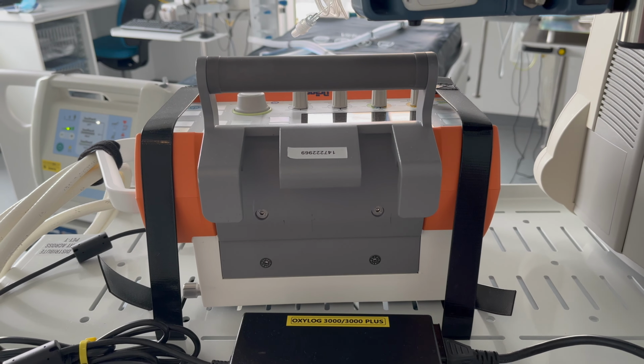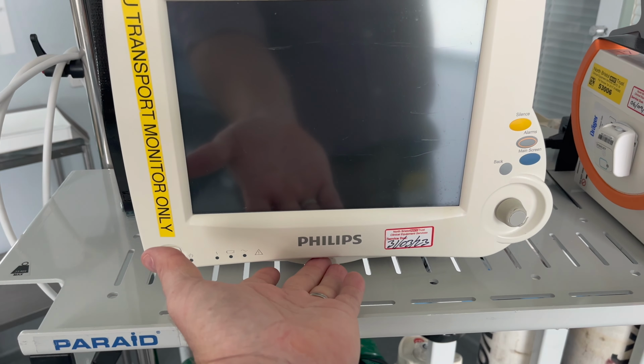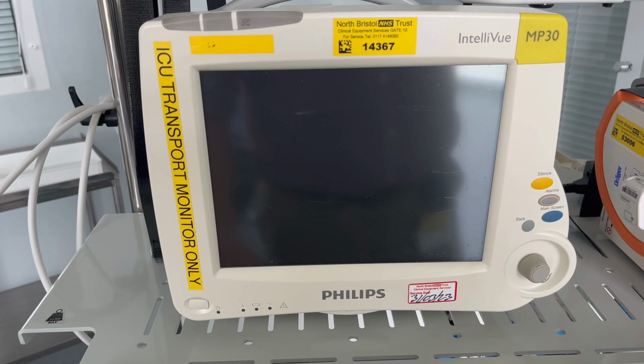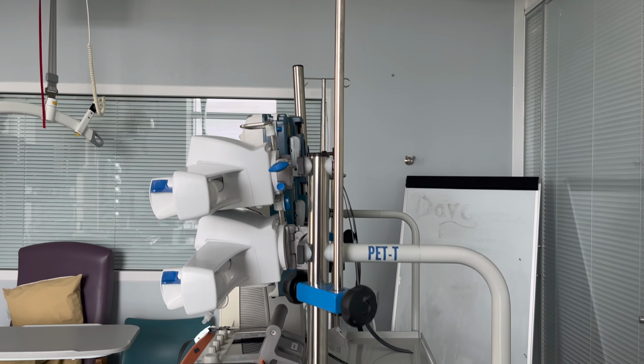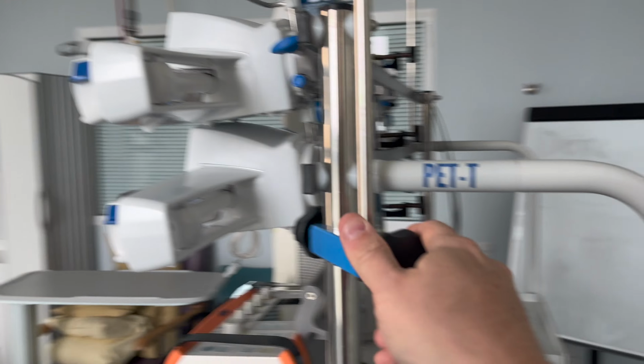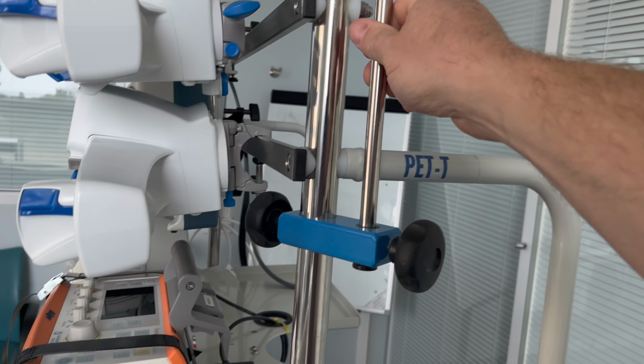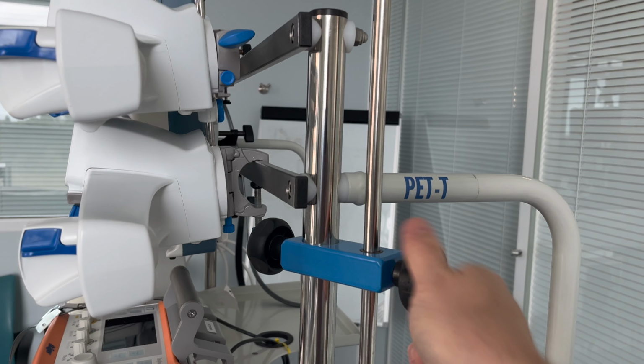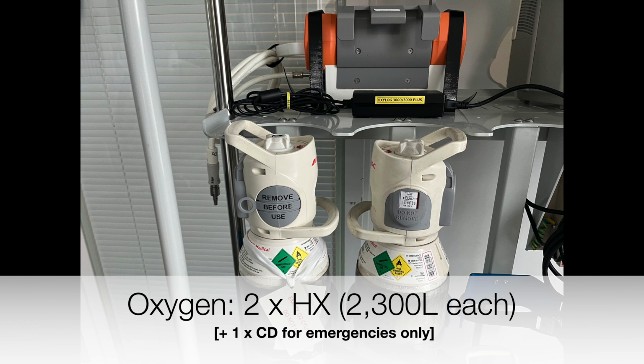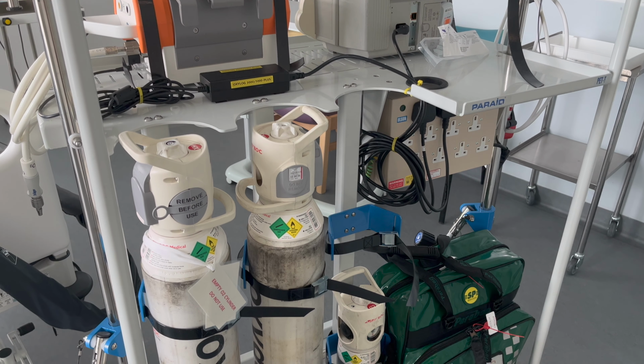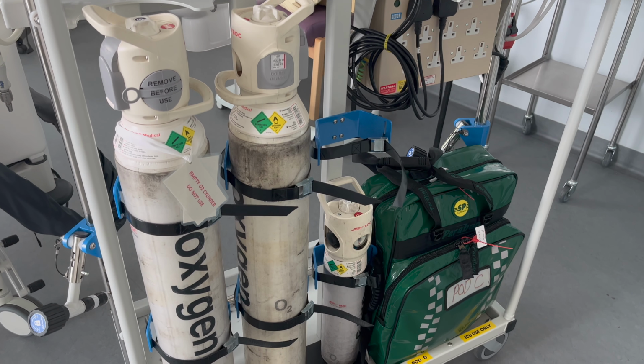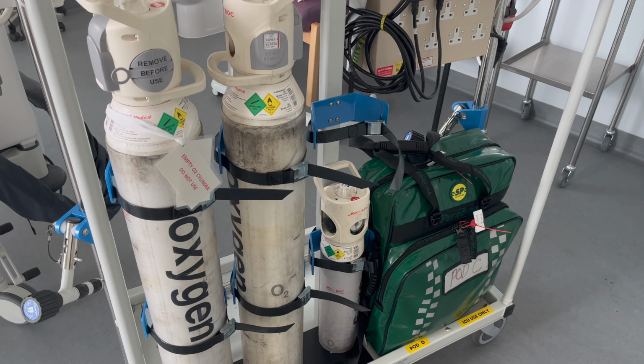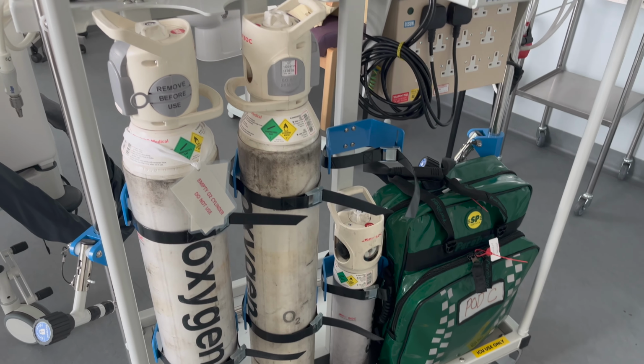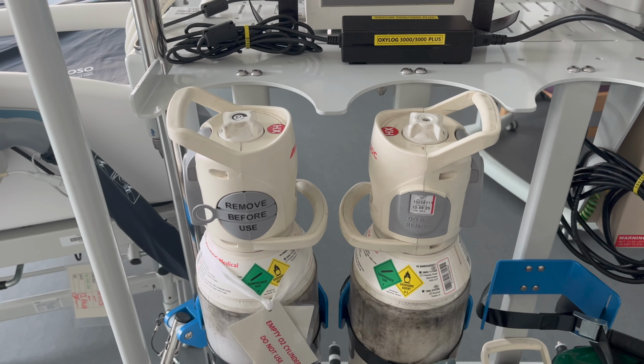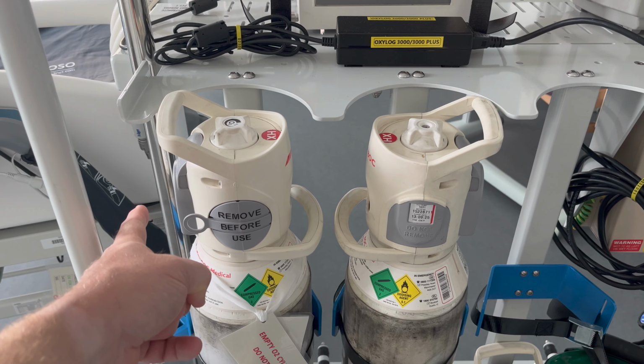The monitor can be removed by pressing the button underneath the Philips logo and lifting it vertically. There are drip stands on each side of the trolley that can be moved by unscrewing the black knob and moving either the mount or the drip stand itself. There are two HX size oxygen cylinders as well as a CD cylinder. Use the HX cylinders in preference and use them until they are empty. When they are, place one of the empty O2 cylinder labels on them and ask the porters to change them. The cylinders should be rotated so that you can access the Schrader connectors in the orientation as you can see.